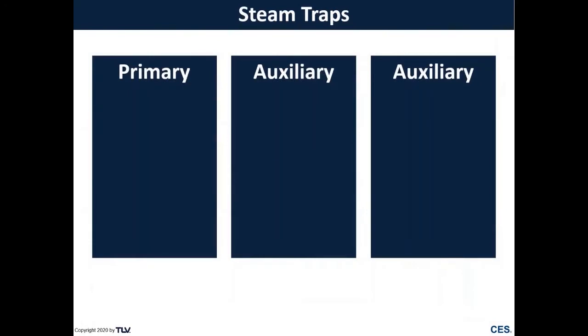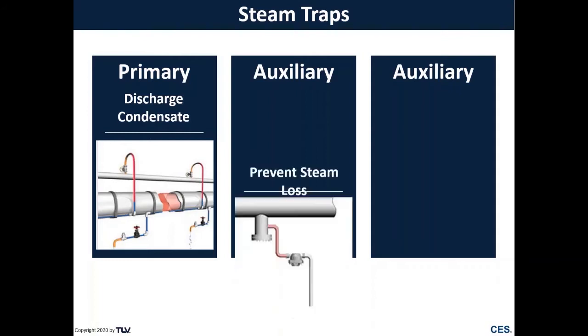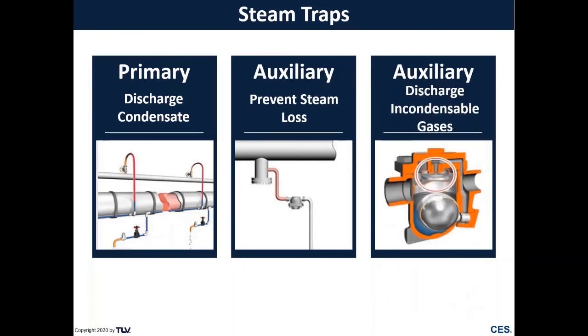If we look at our steam traps, there are three main functions. The first is to discharge condensate — if we're not discharging condensate, we're not performing the primary function. The second is to prevent steam loss — hence the name steam trap — ensuring we operate efficiently. The third auxiliary function is to discharge air and non-condensibles, which gives us faster startup and helps with batch process equipment.